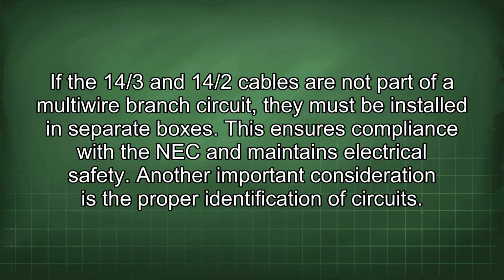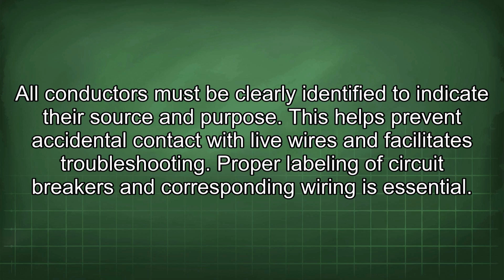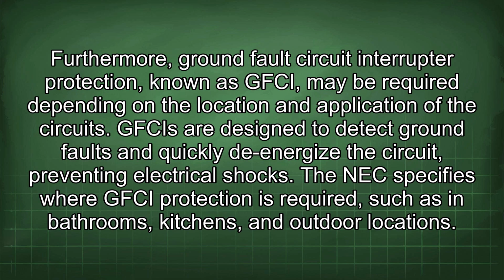Another important consideration is the proper identification of circuits. All conductors must be clearly identified to indicate their source and purpose. This helps prevent accidental contact with live wires and facilitates troubleshooting. Proper labeling of circuit breakers and corresponding wiring is essential. Furthermore, ground fault circuit interrupter protection, known as GFCI, may be required depending on the location and application of the circuits. GFCIs are designed to detect ground faults and quickly de-energize the circuit, preventing electrical shocks. The NEC specifies where GFCI protection is required, such as in bathrooms, kitchens, and outdoor locations.